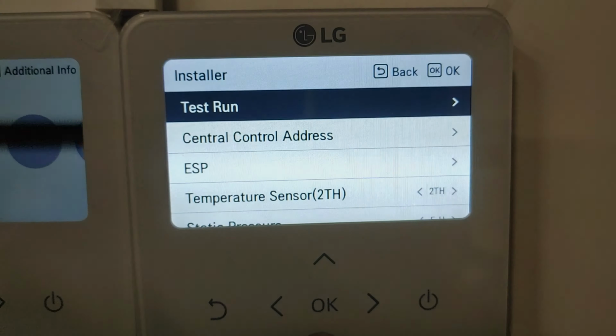It means when user selects high speed of fan on thermostat, the fan in the unit will provide 0.7 inches of water gauge and 2000 CFM airflow with the current selected ductwork. Then we can select the same set value for medium speed and low speed of fan. Now, whichever fan speed user selects, it always will give the same airflow and static pressure.